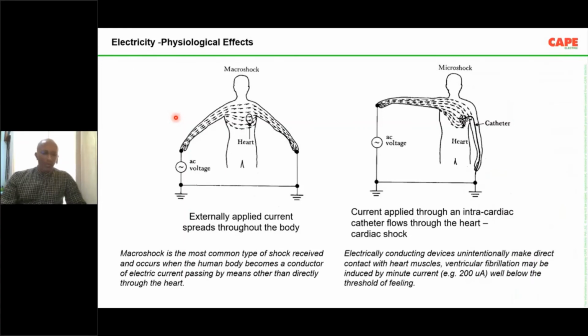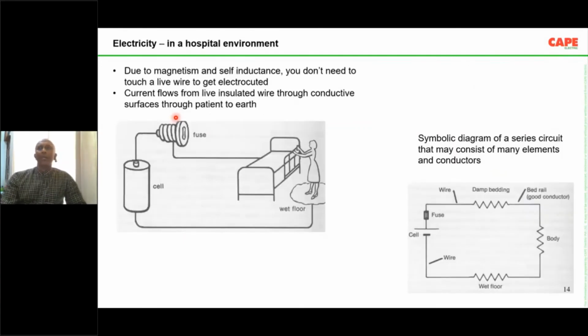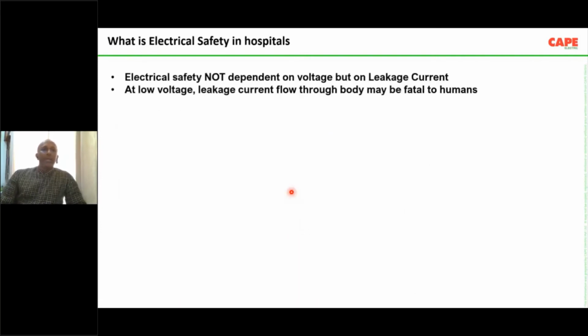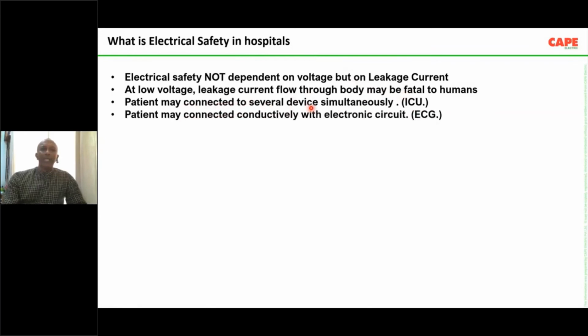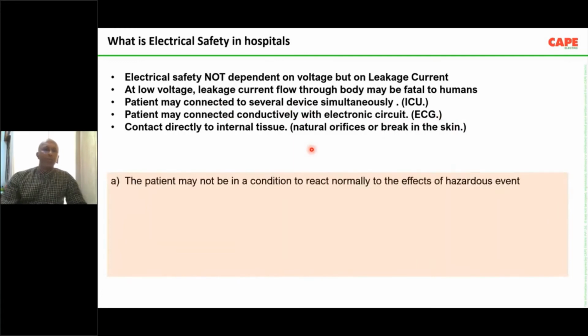Why? Because a current flow through the heart will create a micro shock, macro shock, and problems such as due to magnetism and self-inductance, even a wet floor is enough to create a shock. These are special things. Actually, this has nothing to do with the fire, but this has very much to do with patient safety. Electrical safety is not dependent on voltage, but on the current. At low voltage, leakage current flow through the body may be fatal. Patient may be connected to several devices simultaneously, and may be connected to conductive electric circuits such as ECG apparatus, and contact directly to internal tissues is also often made.